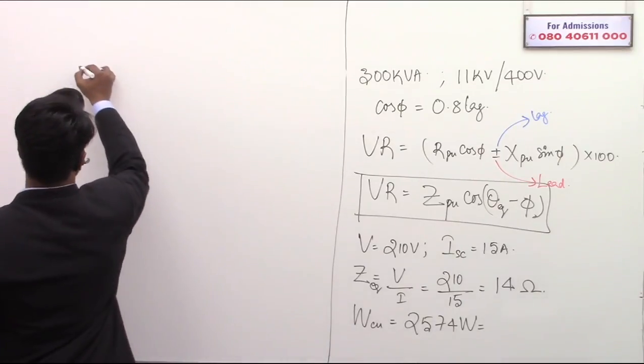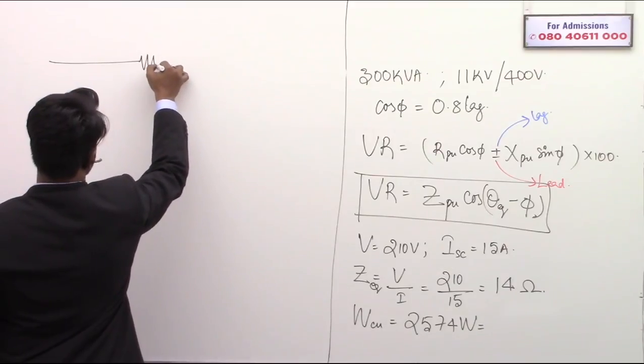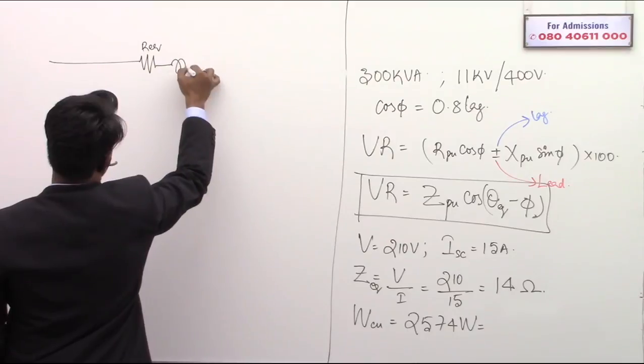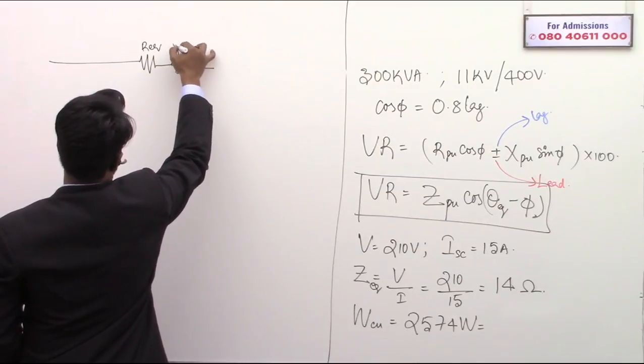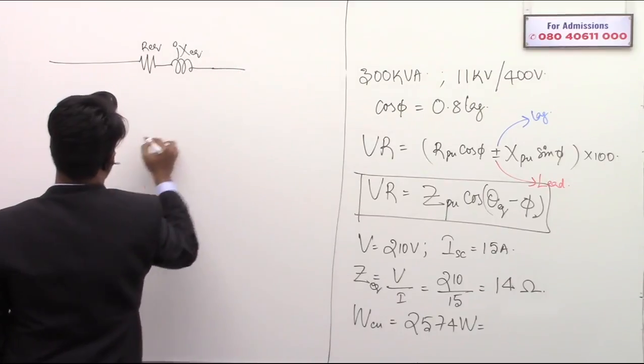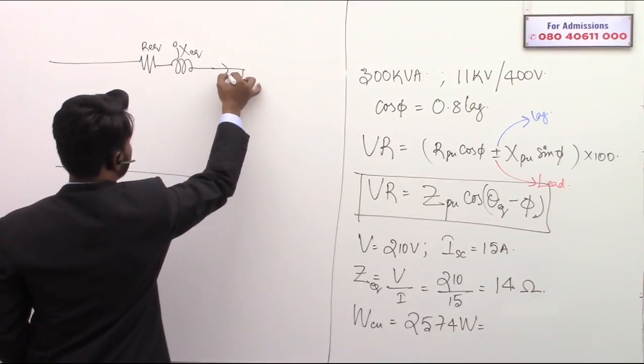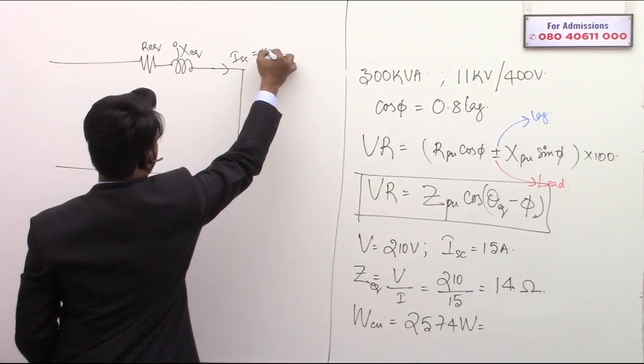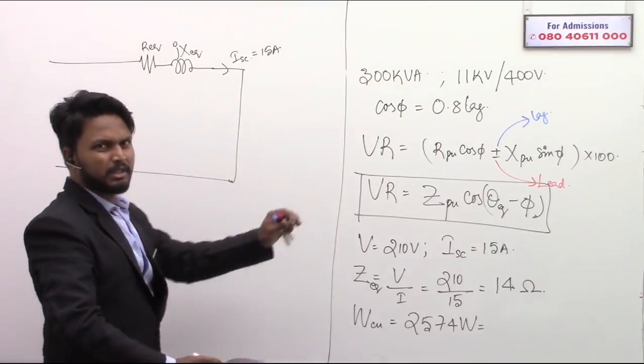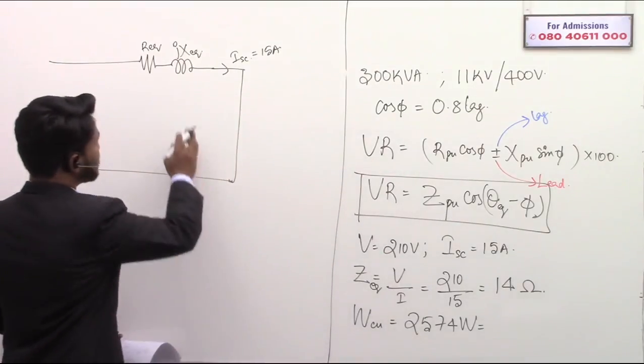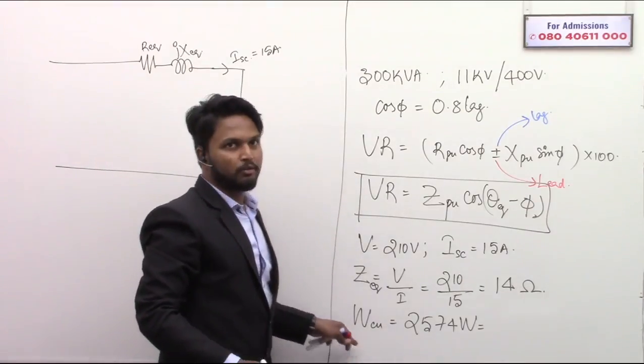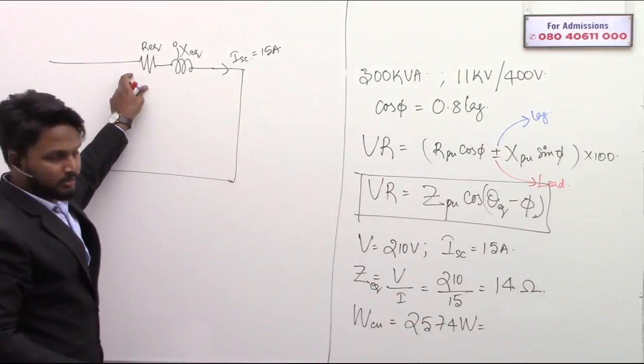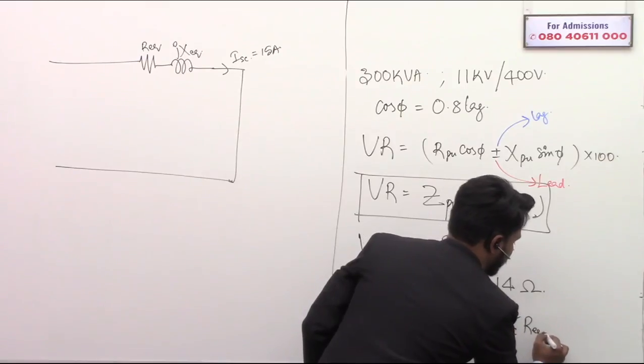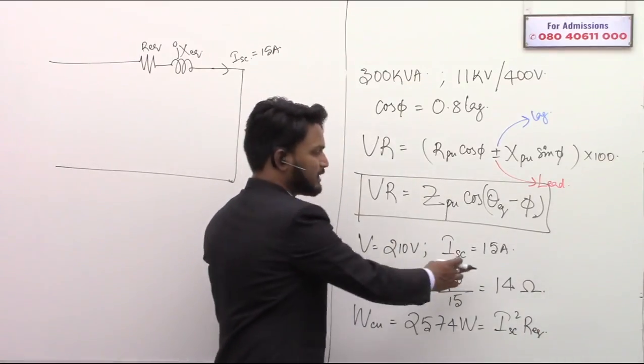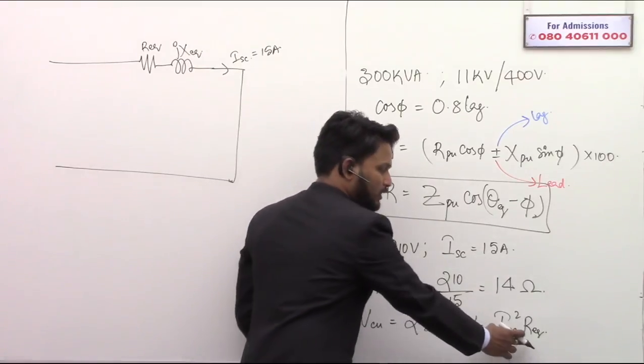What is the equivalent circuit of the transformer? This is R equivalent, and this is j times X equivalent. Through this short circuit, the short circuit current of 15 amperes is flowing, adjusted by adjusting the voltage. So this is Z equivalent. You have to find the value of R equivalent. The wattmeter reads the copper loss, so I_SC square R equivalent is equal to the copper loss. I_SC is given to be 15 amperes. Therefore, you can find R equivalent from this.